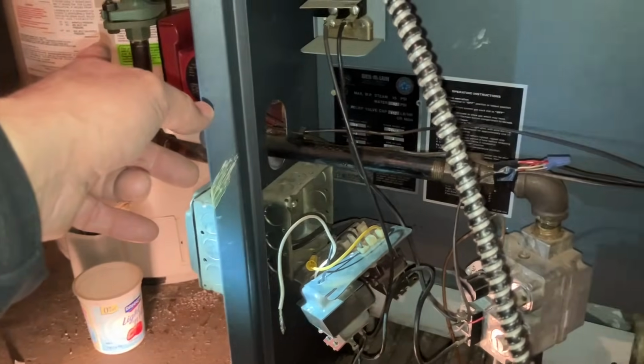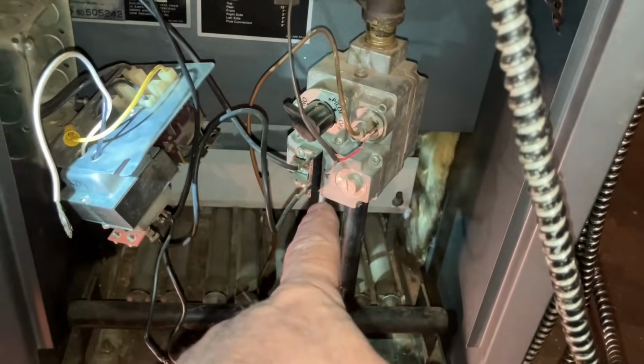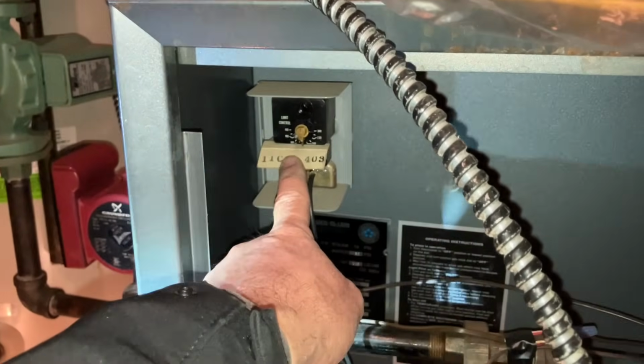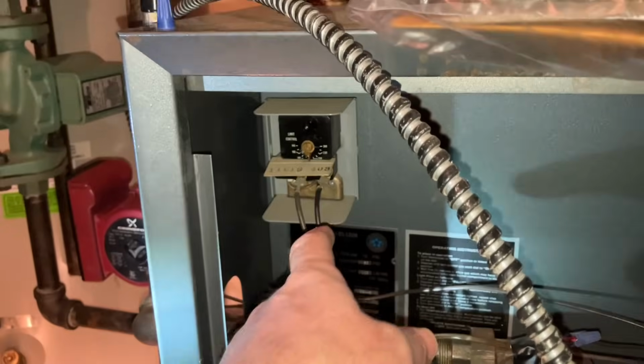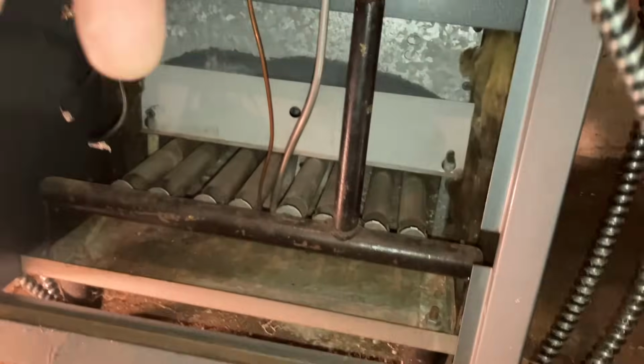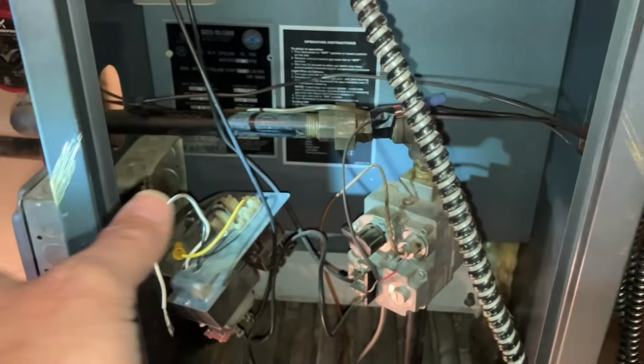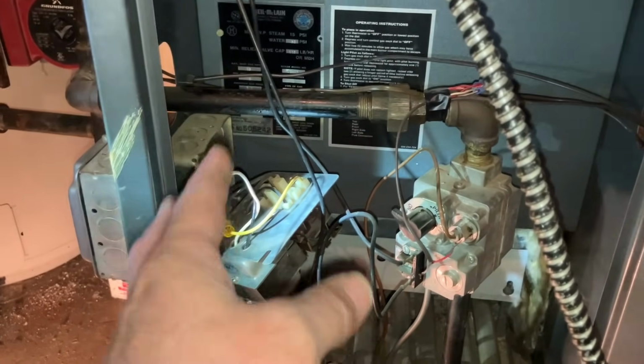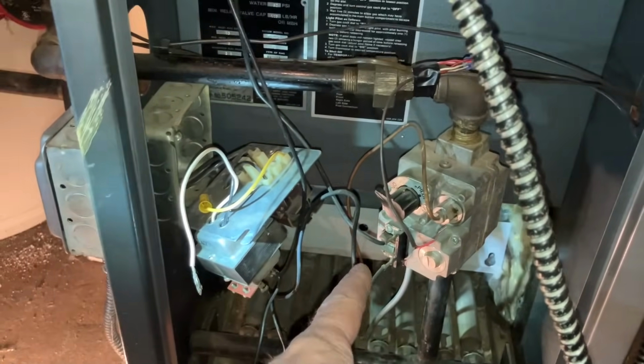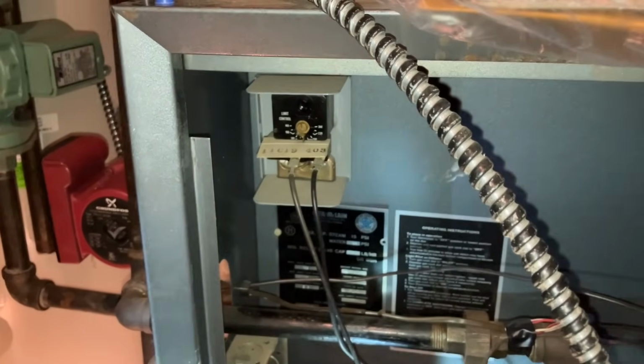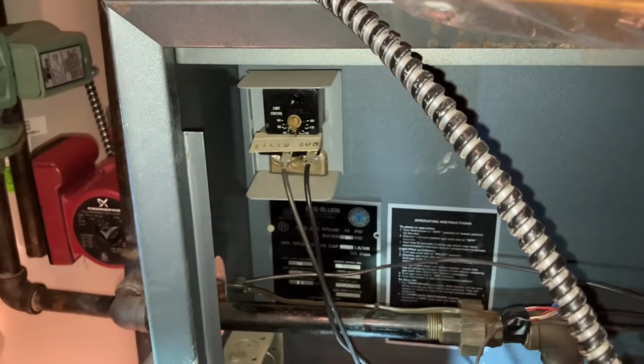So the circulator runs, however, you also need 24 volt circuitry to power the low voltage controls here, like the gas valve. Even though these are switches, this is an Aquastat high limit switch. It still has 24 volts going through it. But your system is actually very simple. The transformer is only giving power to the gas valve as long as the high limit switch is in the closed position. Right? You don't have a rollout switch. You don't have a spill switch on the draft diverter. It's a very simple boiler. As simple as it gets, right?